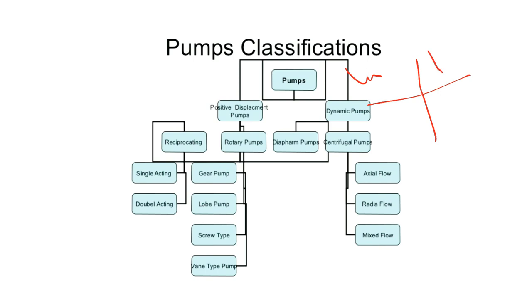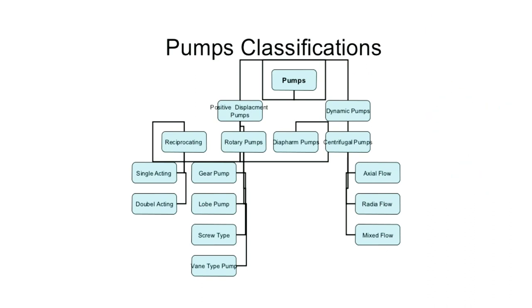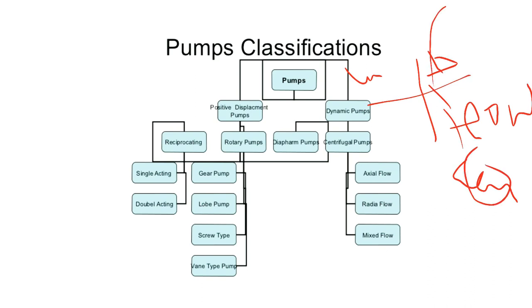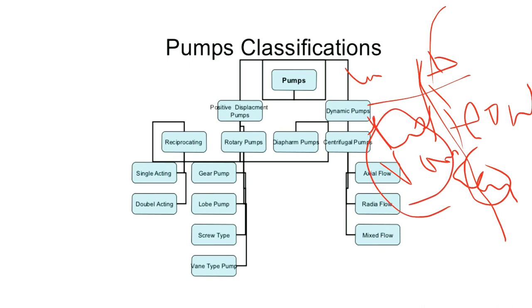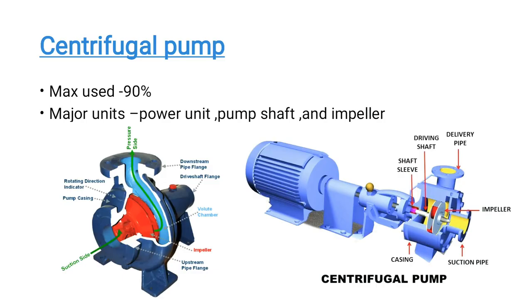In a centrifugal pump, flow varies when we change the pressure — flow is not constant. In a positive displacement pump, flow is constant regardless of pressure changes. This is a very important distinction: centrifugal pump flow varies with changing pressure, while positive displacement pump flow remains constant.